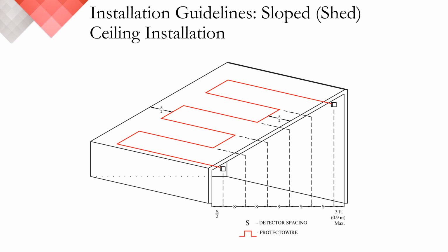In a shed slope ceiling, a row of detectors is required within 3 feet of the high side of the ceiling. Spacing will then follow the requirements for spacing of that ceiling type that you encounter. Spacing is to be based on the horizontal projection of that ceiling.